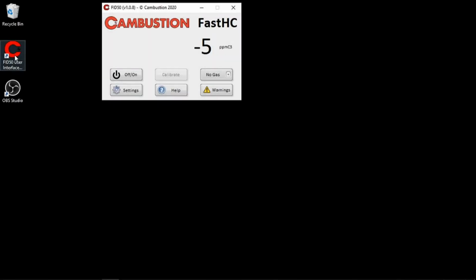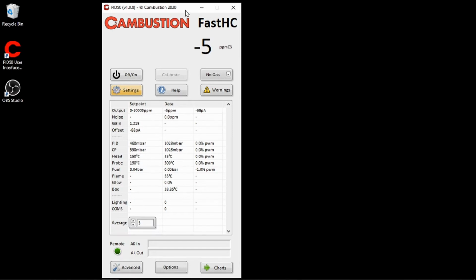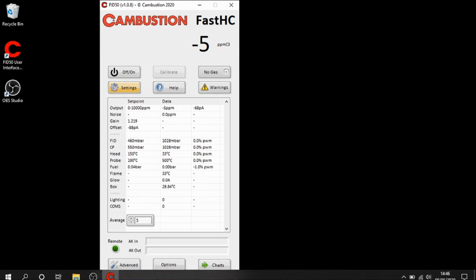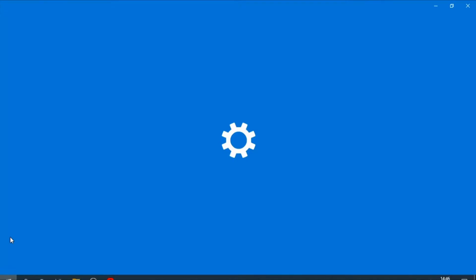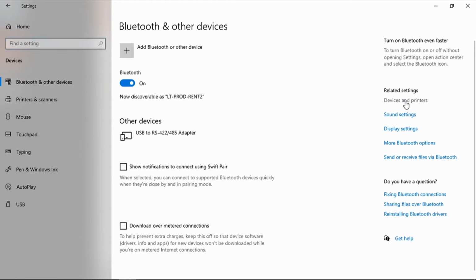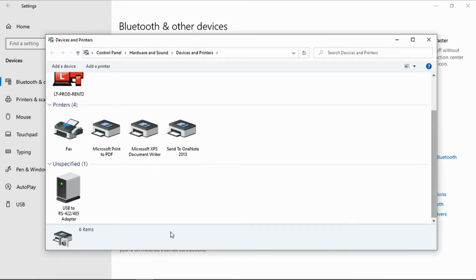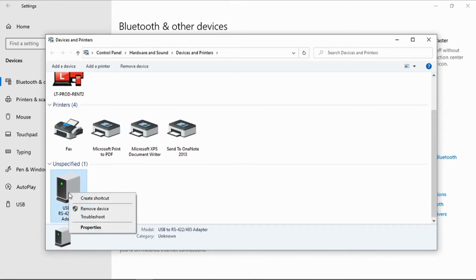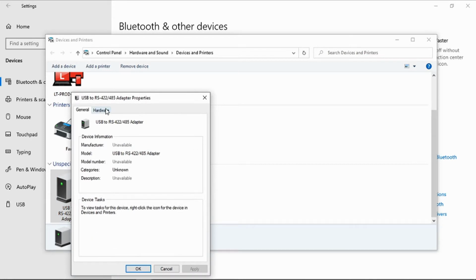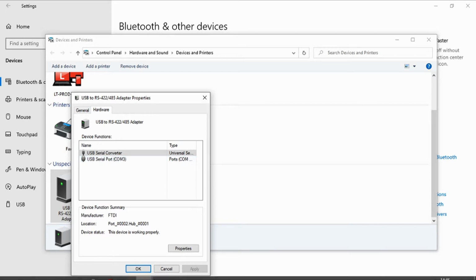If you're supplying your own laptop for running the FID50, then after installing the user interface and the drivers for the USB to RS485 comms kit and the .usf file, which is the set points file for your particular analyzer, it's important to set up the COM port. This is done by finding out which COM port your laptop has ascribed to the comms hardware which we have supplied and you've plugged into one of the USB ports. By looking under devices and printers in your computer settings, you should be able to find the USB to RS485 entity, and if we look in the properties under the hardware, we can see that on this computer it's been given COM port 3.